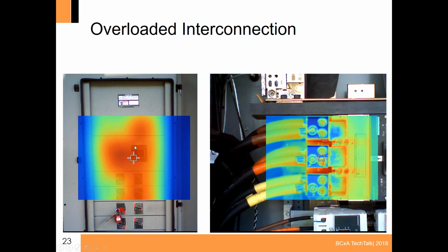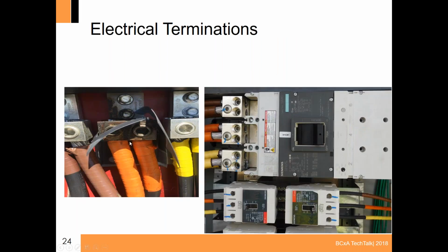So this connection, this electrical panel, was very hot to the touch, and we found out that this breaker was not sized properly. So typically when we size these loads, we're going to size them for 120% greater than their capacity. So that way they'd be operating at normally no more than 80% or so. Electrical terminations, again, same consideration. In this case here, every terminal that we tighten the conductor down, or any electrical termination, there's a specific torque value that we need to follow. And in this scenario, this middle lug was not properly torqued. So that's one of the things we go through during the installation.